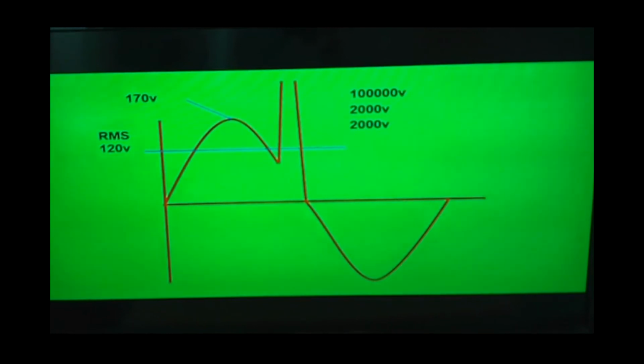Most people have power electronics in their facility. You have solid state equipment, drives, welders, all kinds of equipment today with a built-in power supply. These circuits create what are called harmonic frequencies. These power supplies take current only in a pulse, and that pulse happens at the peak of the sine wave. This creates electrical harmonics, but it also charges and discharges the large capacitors in the system. And as those capacitors charge and discharge, it creates a transient of about 2,000 volts.